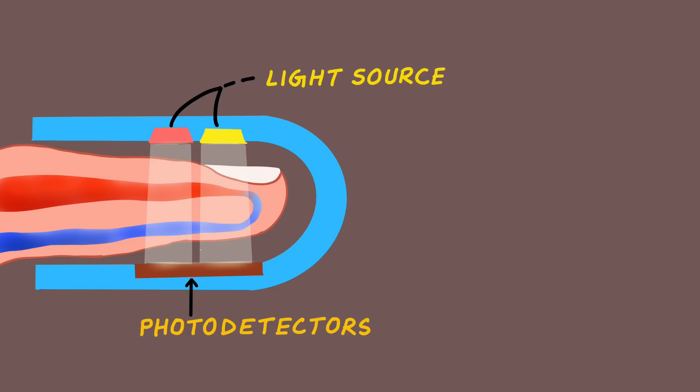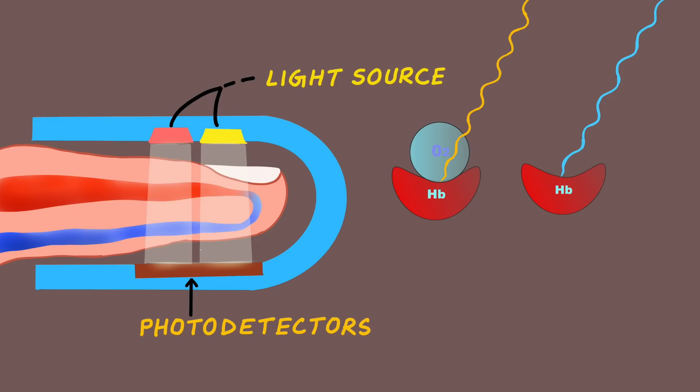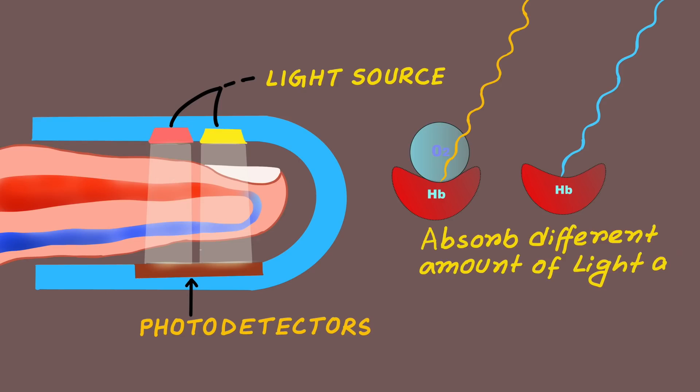The pulse oximeter uses the property that oxyhemoglobin and deoxyhemoglobin absorb light of different wavelengths in a specific way. Oxyhemoglobin and deoxyhemoglobin absorb different amounts of light at different wavelengths.